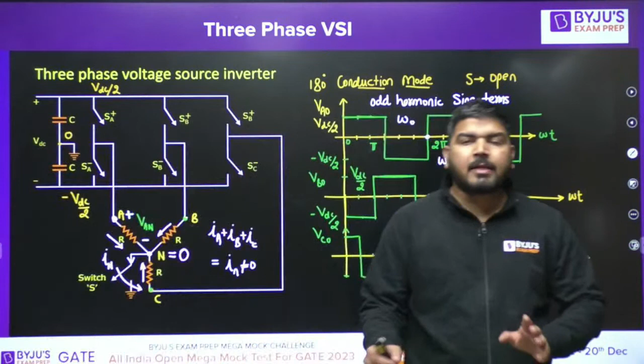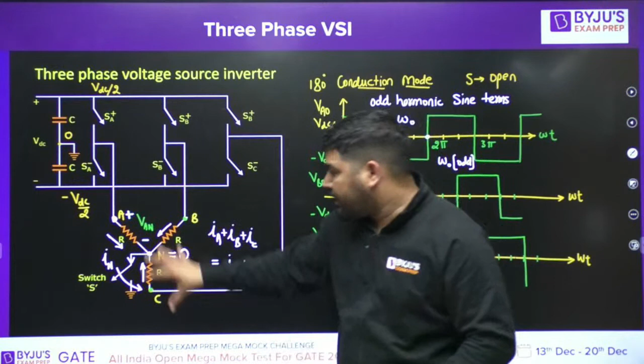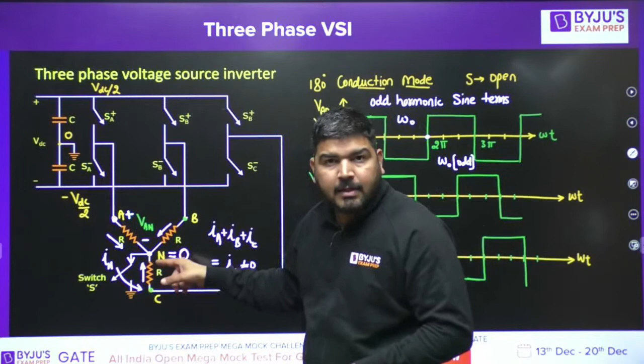If the switch is closed, many things will change. Line voltage will not change, phase voltage will change. This is the phase voltage, and it contains triplen harmonics. Since the phase contains the triplen harmonics, the phase current will also have the triplen harmonic. Every phase has triplen harmonics, and if you try to add them, the sum will not be 0. The sum of these currents will be only the triplen harmonic current. The fundamental will cancel, the 5th will cancel, only the 3rd, 9th, 15th, the triplen harmonic current, will not be zero, and that current will flow through the switch. I hope you understood it.